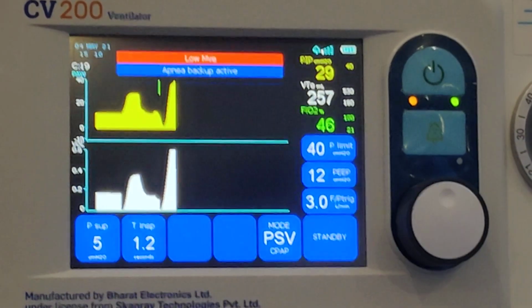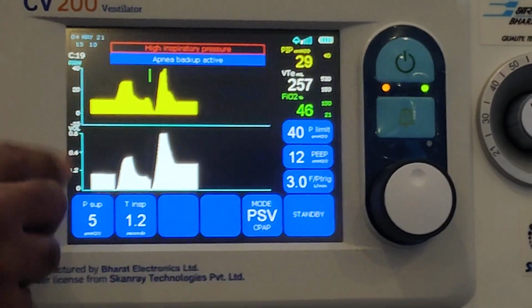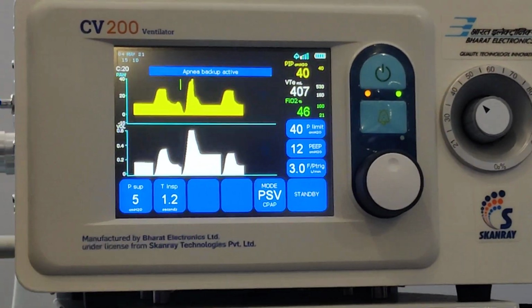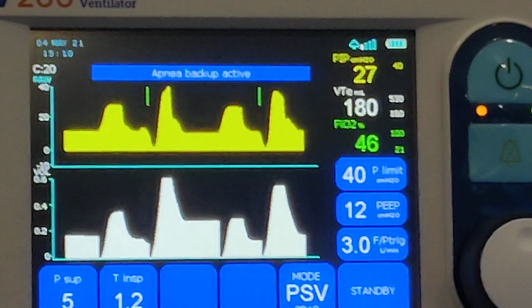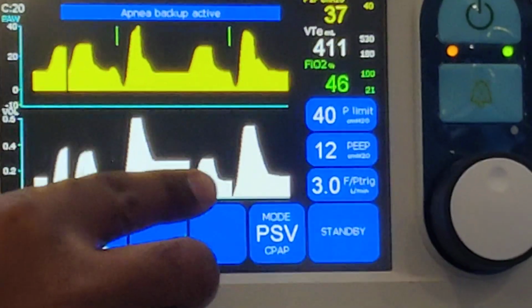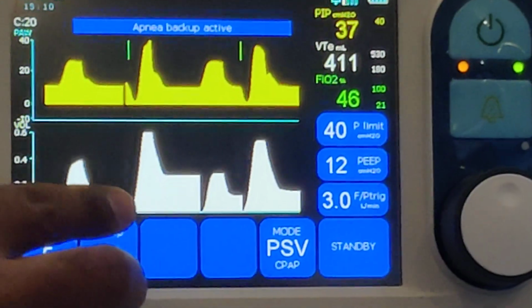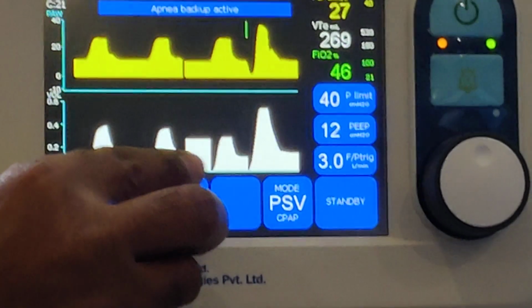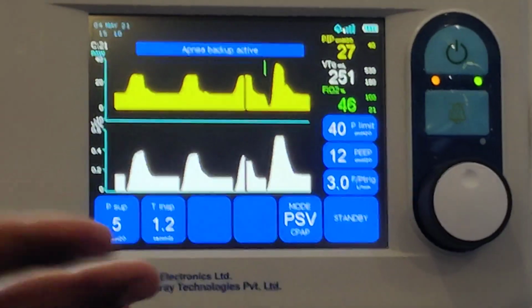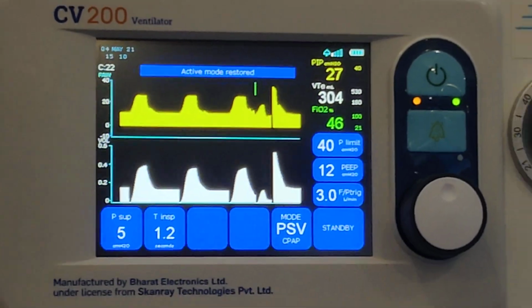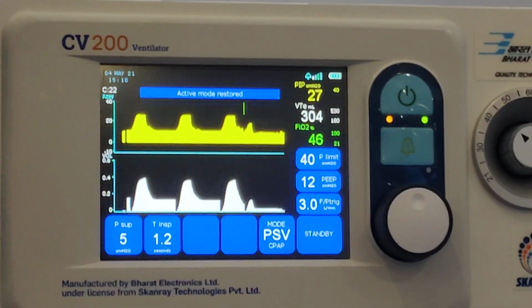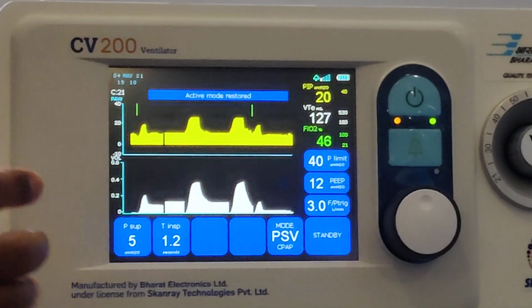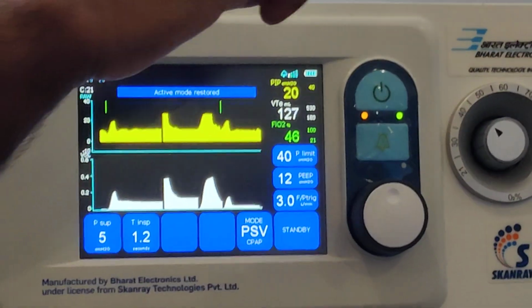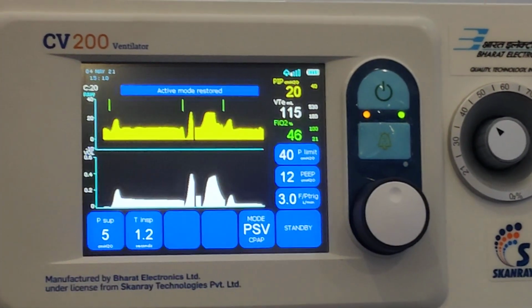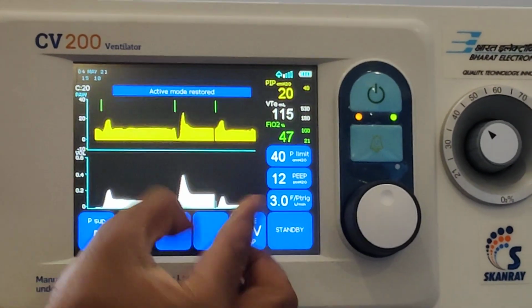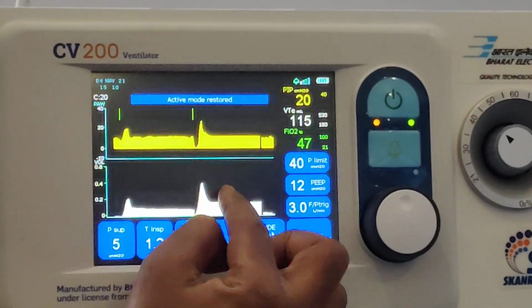Can you see this volume, like 200 ml, 400 ml, 600 ml? This one is the inspiratory part, this one is the expiratory part. Usually the inspiratory and expiratory parts should be of similar fashion, like a proper shaped mountain. As our connector is broken, you can see the inspiratory part is going like this, but there is a lot of leak in the expiratory part. Can you see this? This much volume is leaking.